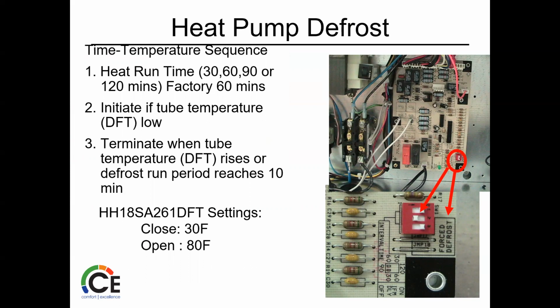Terminates when the DFT rises, or if it ran for 10 minutes. Obviously, if we're not defrosting long enough and we're defaulting out, then we got another problem, right? Do we need low ambient here? What's going on? Because that's a problem. But yeah, typically those defrost settings, they close at 30, open at 80. Again, sometimes there's a differentiation there between what unit and how new or old it is, but that's a pretty average amount.